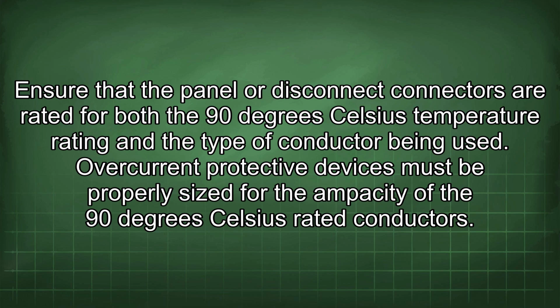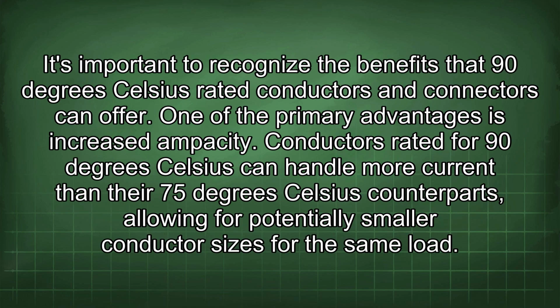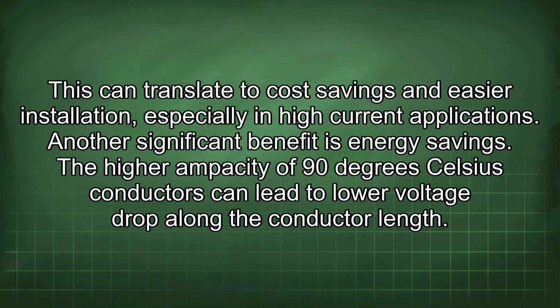Overcurrent protective devices must be properly sized for the ampacity of the 90 degrees Celsius rated conductors. It's important to recognize the benefits that 90 degrees Celsius rated conductors and connectors can offer. One of the primary advantages is increased ampacity. Conductors rated for 90 degrees Celsius can handle more current than their 75 degrees Celsius counterparts, allowing for potentially smaller conductor sizes for the same load. This can translate to cost savings and easier installation, especially in high current applications.